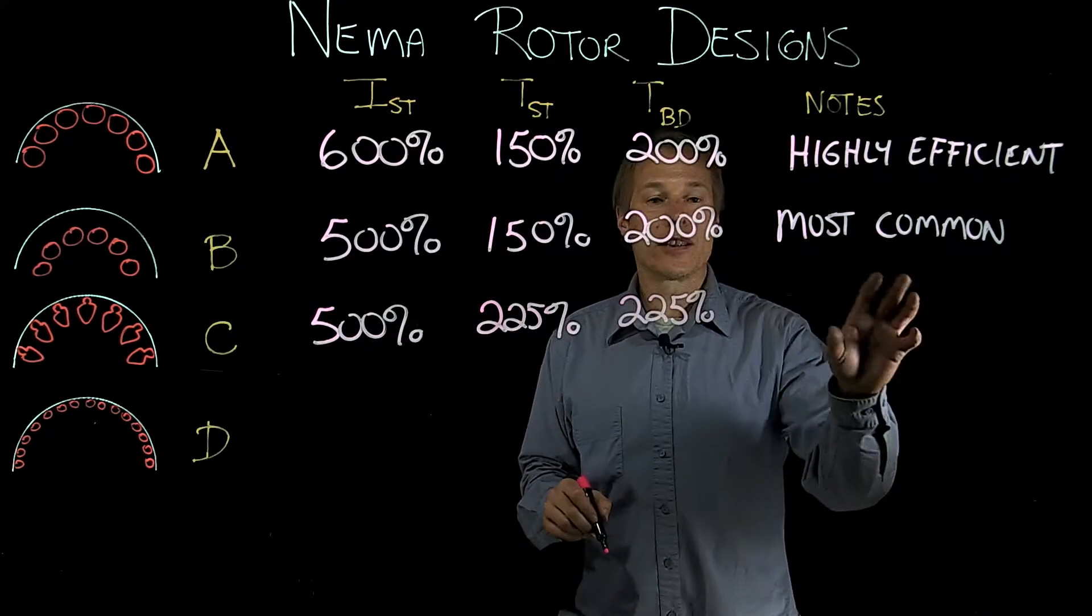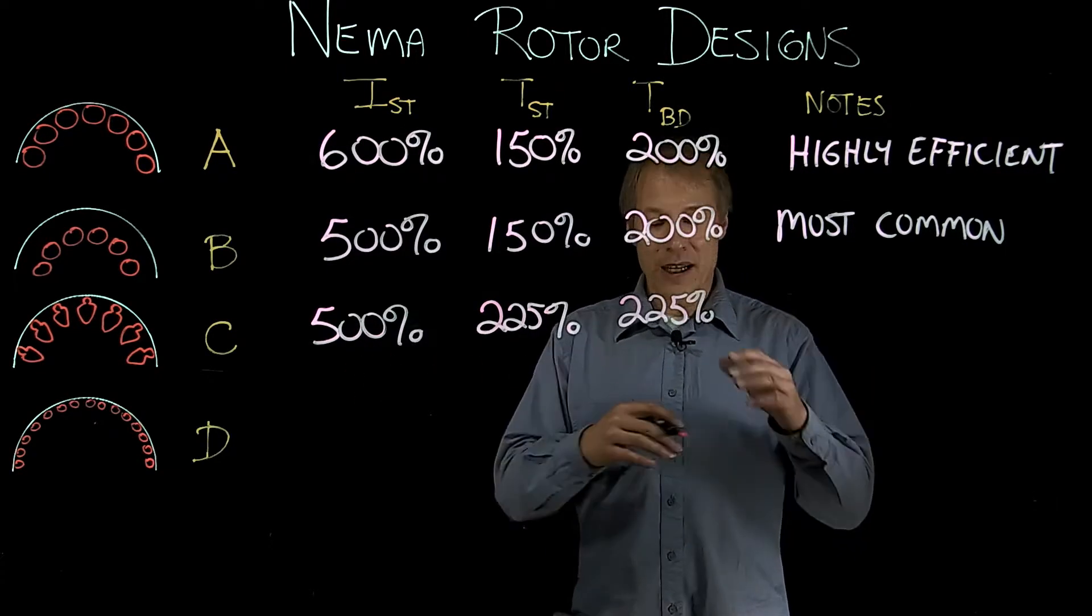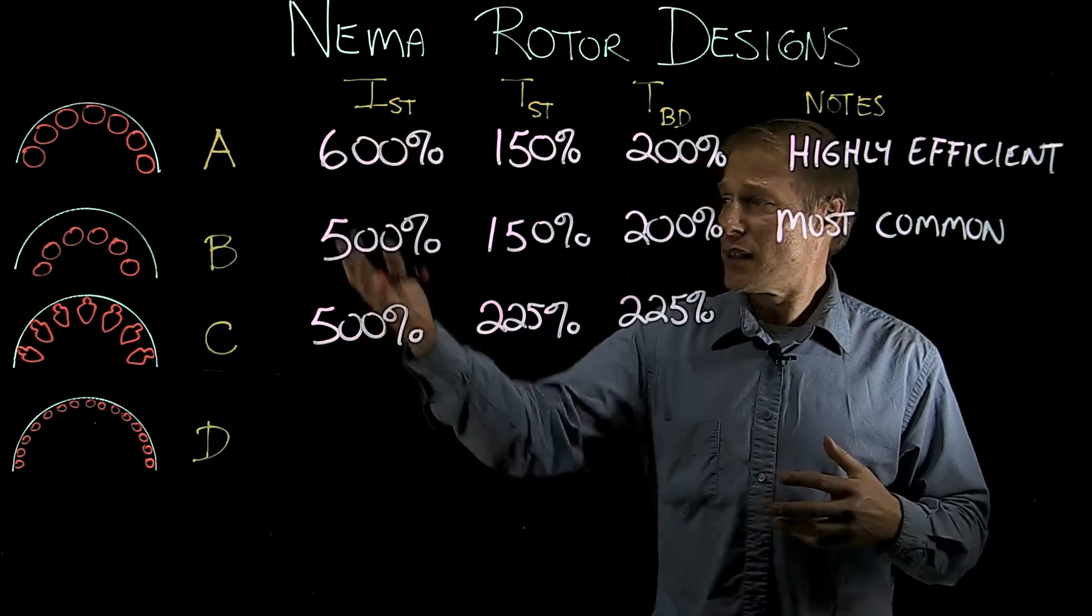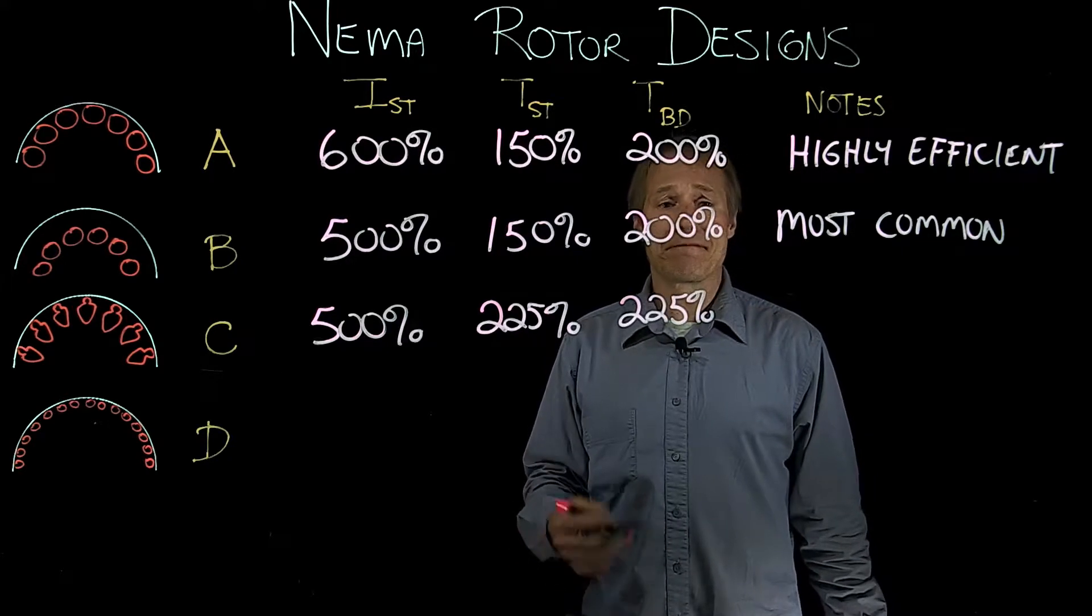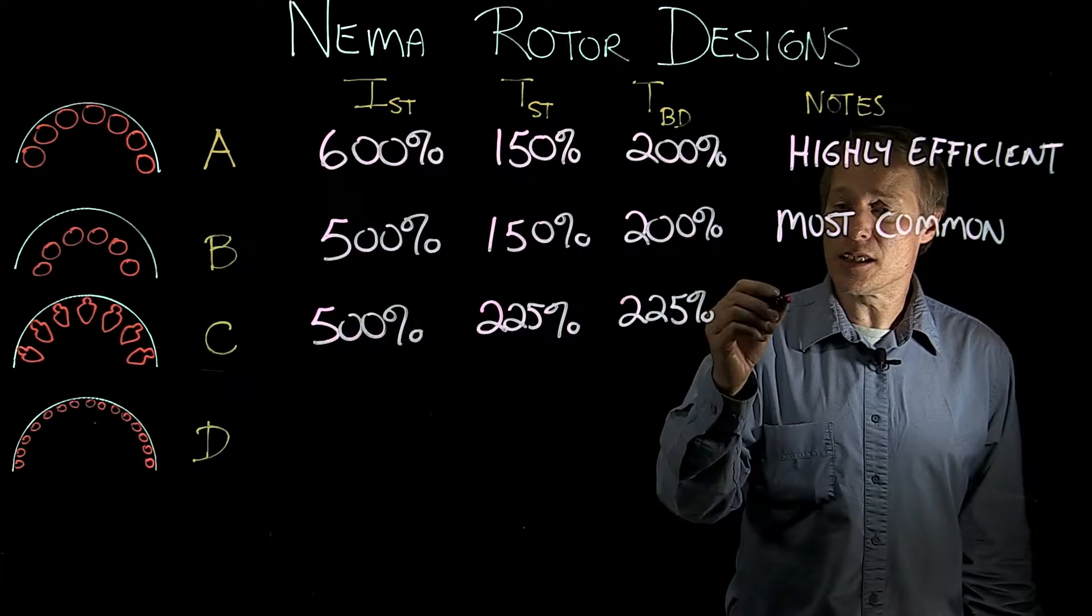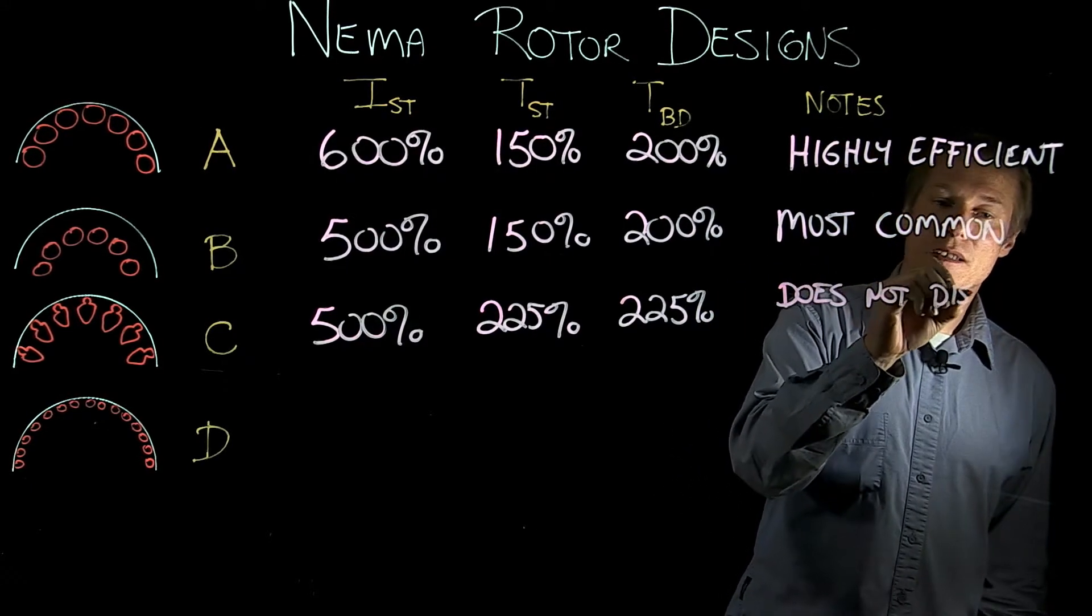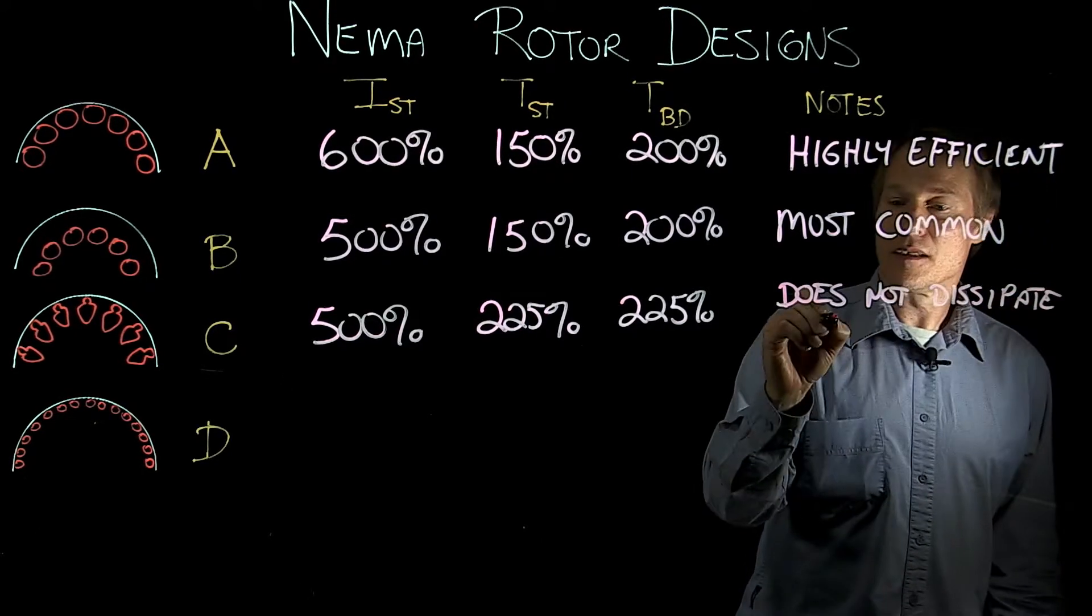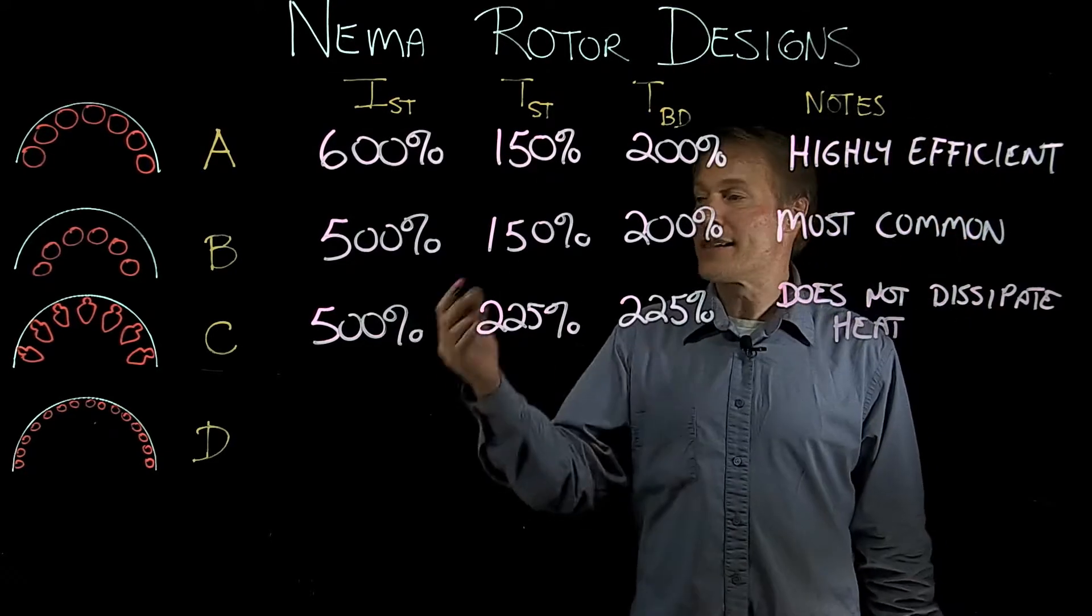Now as far as the characteristic, beside it being a double squirrel cage design, because of that double design, it's not going to dissipate heat as well as the single cage designs, so it heats up a little bit more. So it doesn't dissipate heat, or heats up, let's say, does not dissipate heat as well as the A or B.